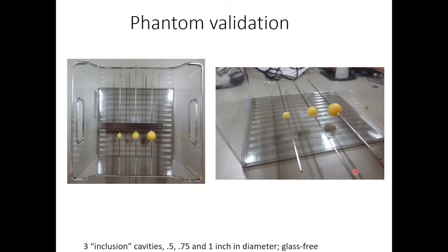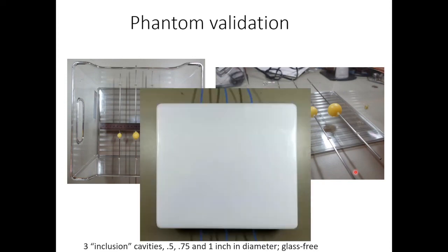And this was a way to test it. This is jeweler's wax, which both melts and dissolves in water, which was interesting because we cast these balls in a silicone mold, and then we put them through the wall of this container and then poured silicone rubber, that is typical phantom for us, around them. And then we drew the metal tubes and then pumped in hot water to dissolve it. So we ended up with what we call a phantom that has cavities with tubes attached to them, and we can propagate solutions of ink and milk, or ink and something called Intralipid, that's a lipid suspension, which simulate optical properties kind of like tissue.